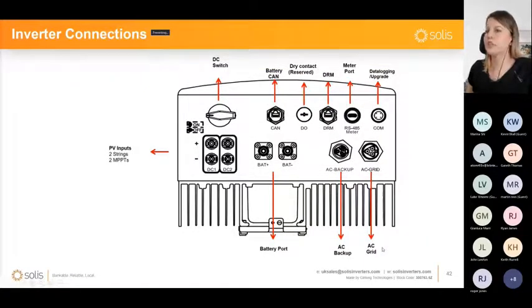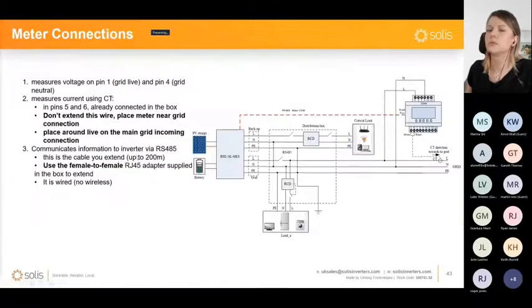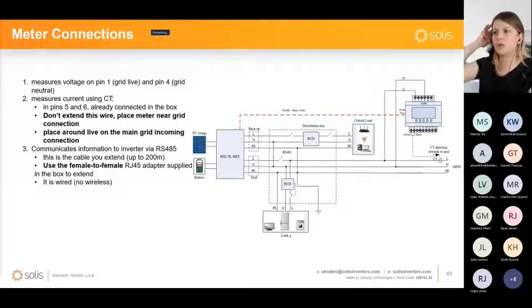In terms of inverter connections, I think we already went through this quite a few times, so I won't take too much of your time with it. I'm just going to talk a little bit more about the meter connections, which, as I told you, are so important. The meter is one of the pieces of the puzzle that needs to fit in the right spot in order to have the system work properly. So always the meter is the one that needs to monitor the consumption on the grid connection point, so it can always know what is going in and out.